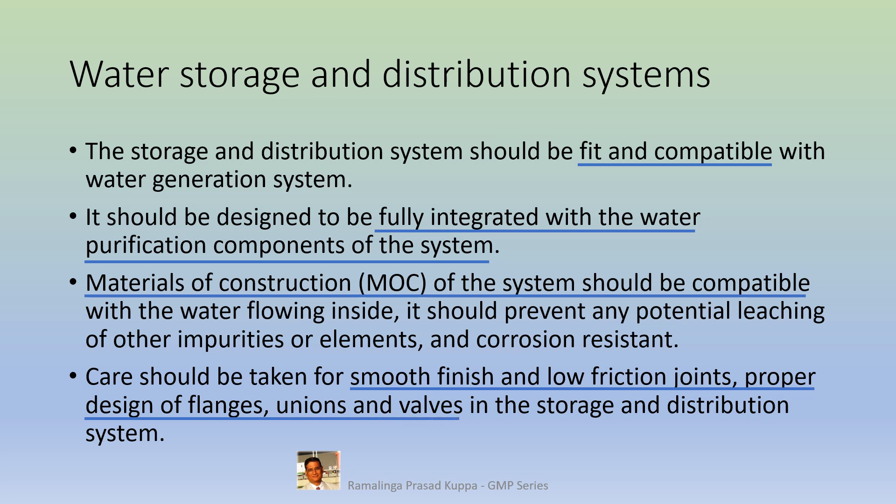unions and valves in the storage and distribution system. The internal finish should have an average surface roughness of not greater than 0.8 micrometer Ra. When stainless steel is used, mechanical and electro-polishing techniques may be employed. Electro-polishing improves the resistance of stainless steel materials to surface corrosion.